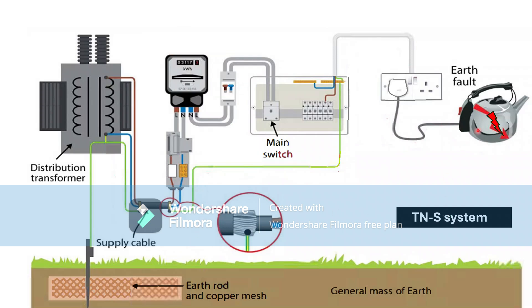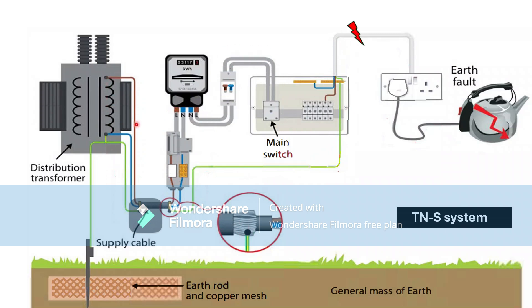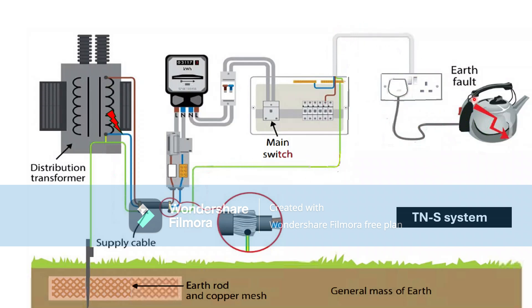In the case of a TN-S system, if there is a fault in an appliance, the fault current will start flowing. It goes through the line, through the CPC to the earthing conductor, through the armor, back to the supply transformer, into the meter, from the meter to the main switch, and then it trips the circuit breaker.